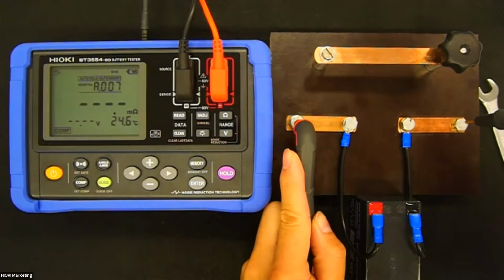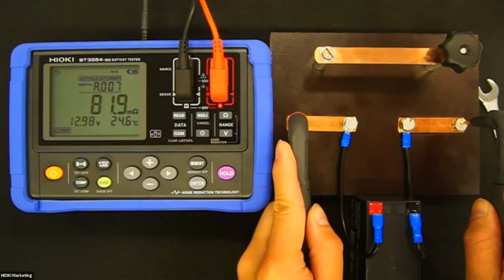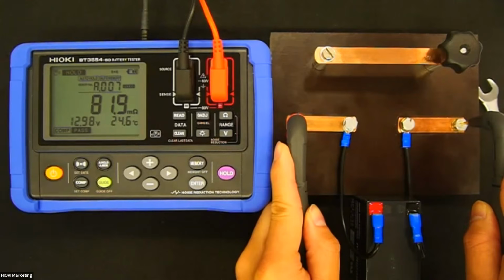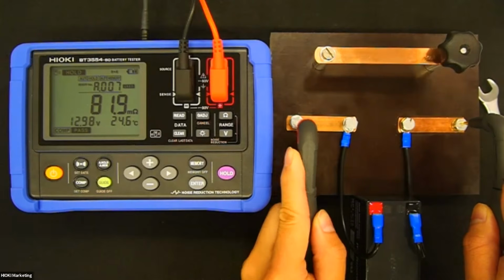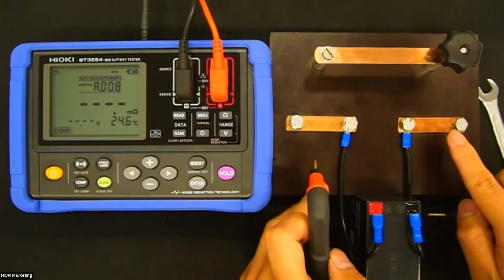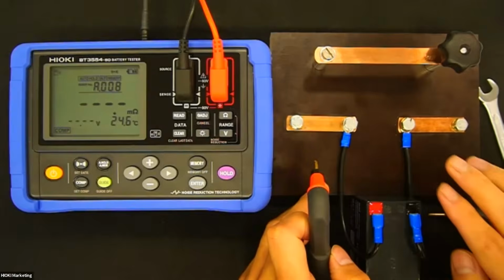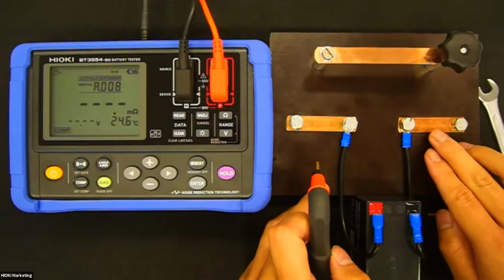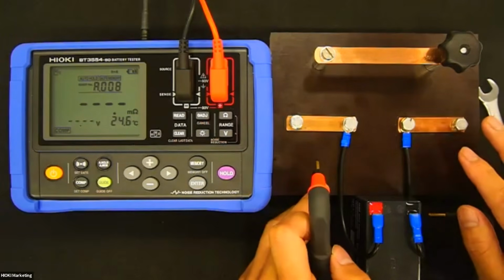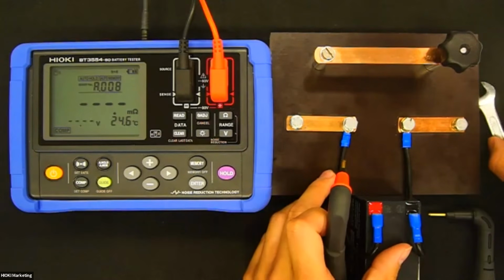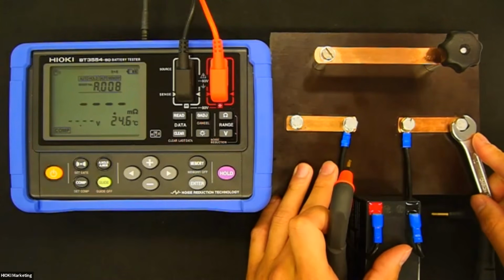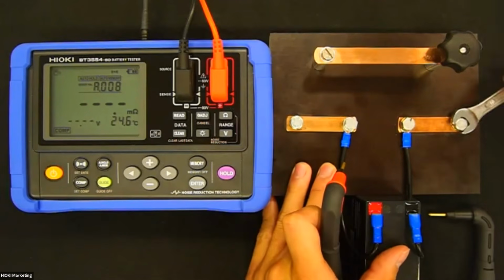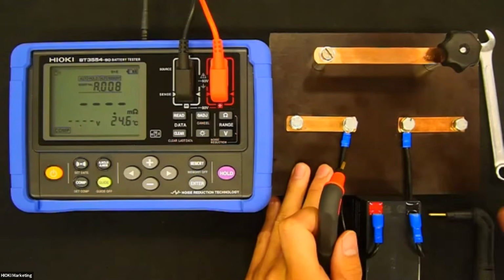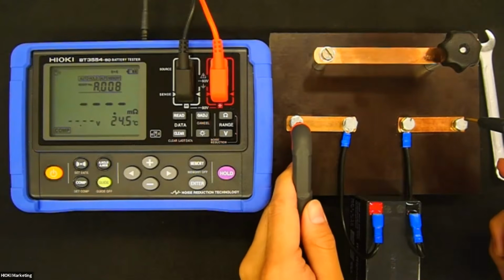Okay, here is the bus bar, and you have to check the resistance via the bus bar and board. Now the device shows a pass. But checking connection resistance is required for battery maintenance, because if the connection has a problem, you can't correctly judge the battery resistance. You may have already noticed, if one bolt is loosened, we will get a different result.